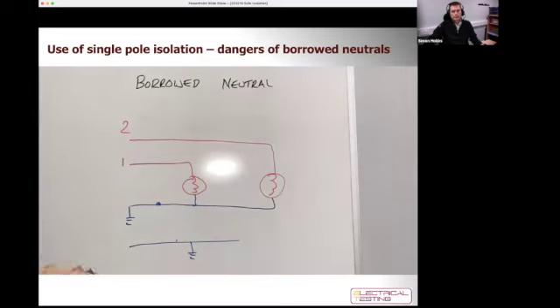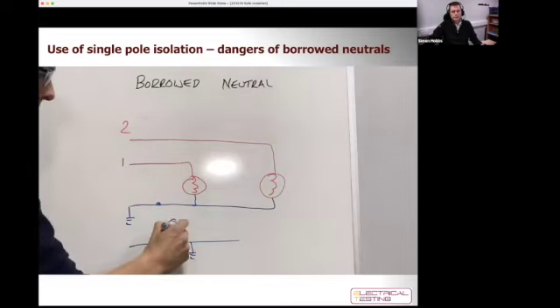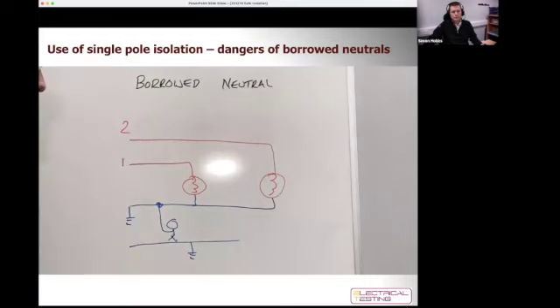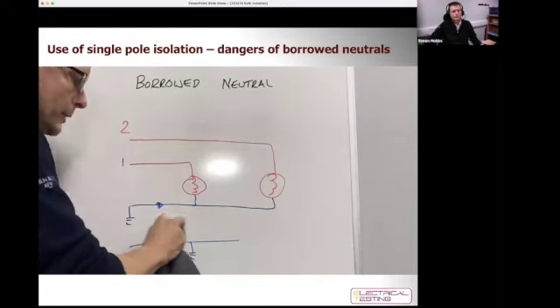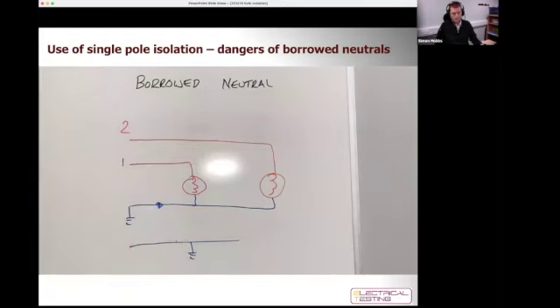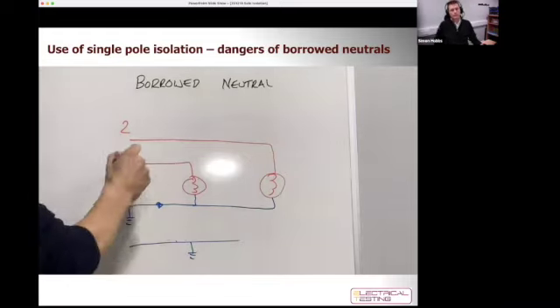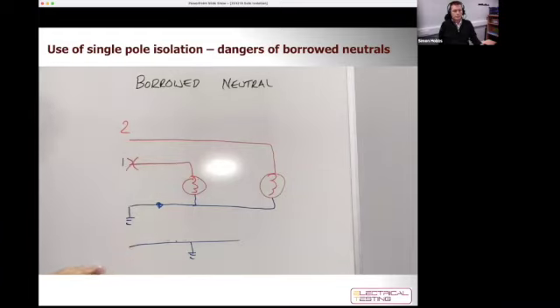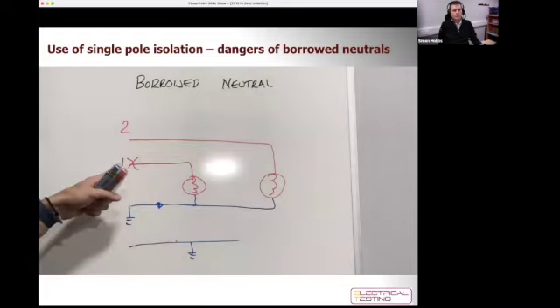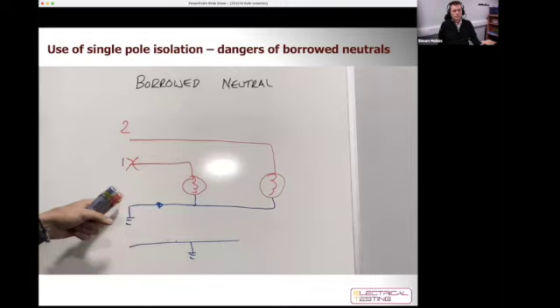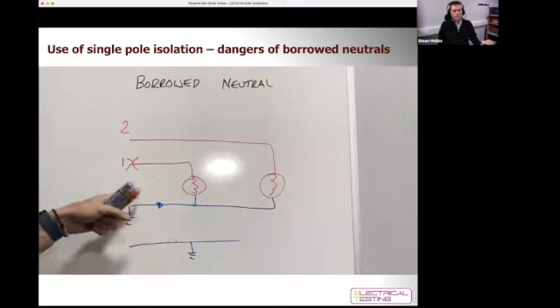So again, if I'm here working and I can touch the neutral, I won't get an electric shock. Everything's functioning satisfactorily from an electrical point of view. The problem with borrowed neutrals occurs when I start doing some work. In this instance, let's say on circuit 1, I'm going to isolate the line conductor, switch off the circuit breaker at the distribution board. So I've switched off my circuit breaker and I've now isolated circuit 1 to carry out my work on.